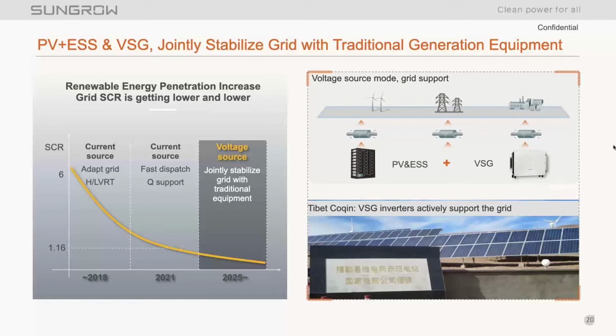Even though it's not traditional, it's still gaining momentum. So if we look back around 2018, we can see that the short circuit ratio of the grid was somewhere around 6 in a lot of these test cases. Okay, so with that current source, what we had to do was adapt to the grid for high and low voltage ride through, and make sure that stability was present there.